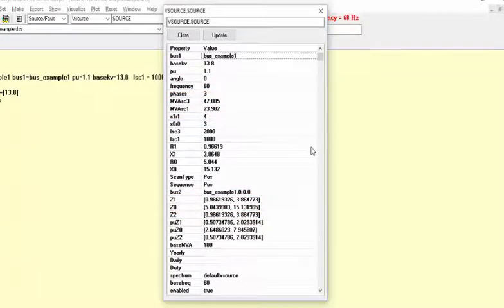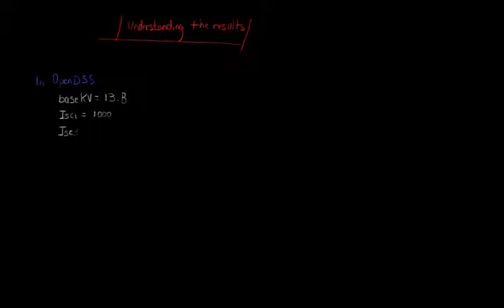As you can see, the values of MVASC1, MVASC3, Z1 and Z0 have changed in accordance to the values of ISC1 and ISC3. Let's understand the values presented on this table. In the example created, we have set the basekV equal to 13.8, single-phase line-to-ground short-circuit current equal to 1000 and three-phase short-circuit current to 2000. We have already deduced some expressions based on the single-phase line-to-ground and three-phase faults, which are summarized below as 1, 2 and 3.